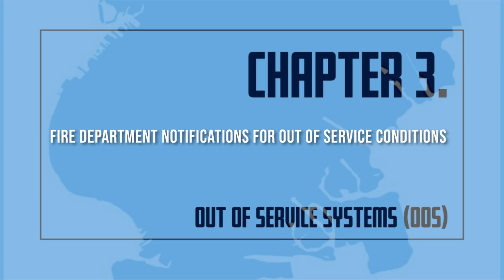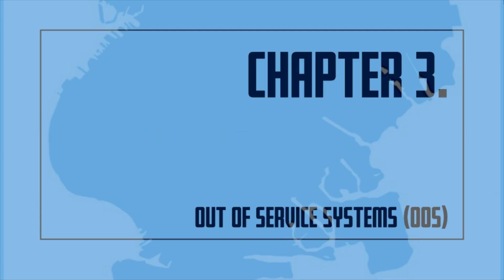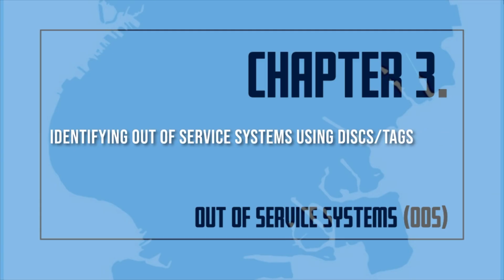Fire Code 901.7.5. Identifying out-of-service systems using disks/tags. Systems that are out of service, both planned and unplanned, shall be immediately identified by placing a tag at each of the following locations: fire department connections, system control valves, the fire command center, or other clearly visible locations in the lobby of the building, indicating which system or part thereof is out of service.